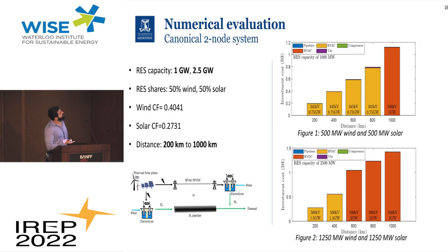Starting with the canonical 2-node system at 1 gigawatt capacity, we vary the distance from 200 to 1,000 kilometers. At 1 gigawatt, HVAC remains competitive up to 800 kilometers, but beyond that, the high cost of cables and HVAC systems, and the reactive power requirements, tip the scale in favor of HVDC, consistent with existing studies.